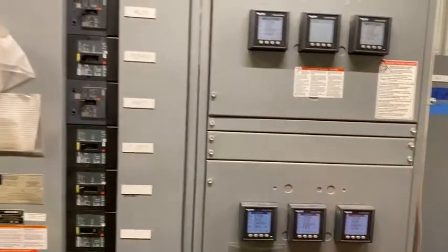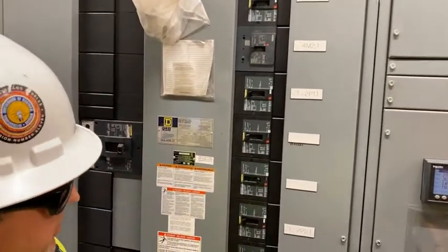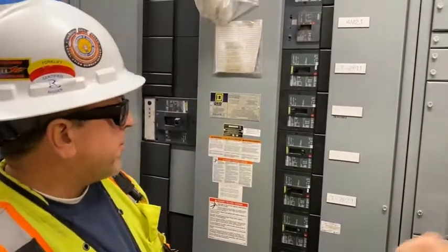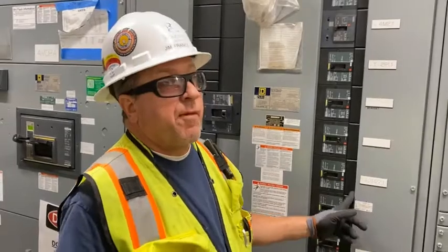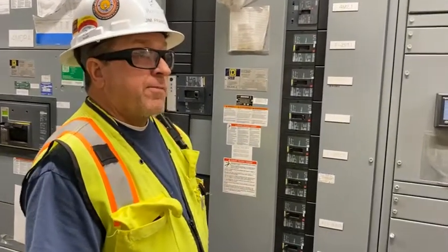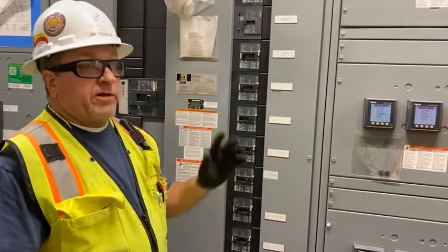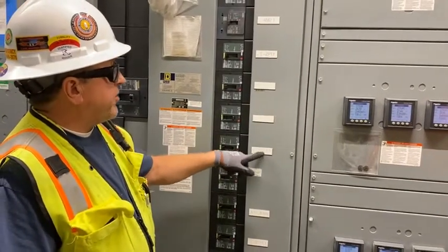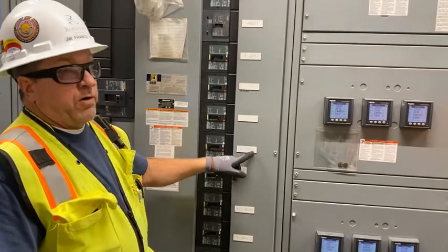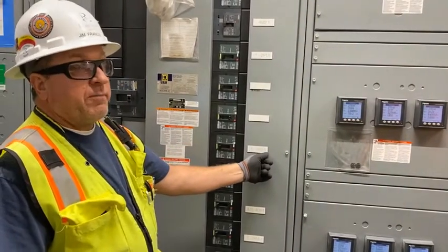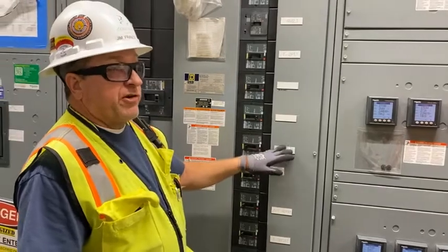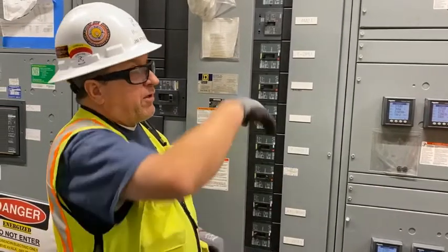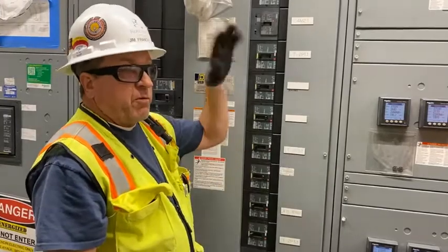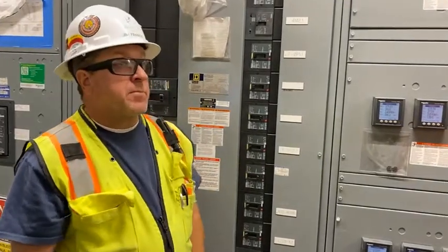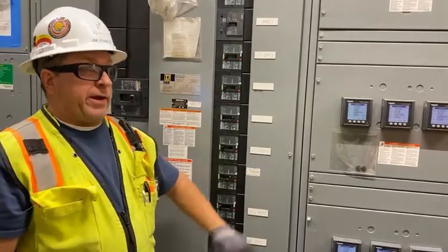So all these here, they're tied to a panel, but like throughout the building too, and electrical rooms and stuff. Well, these are monitoring, for instance, the panels in the rooms, hallways and stuff, up in the electric room. One of these is going to shut one of those down. Yes. If you look at the single line riser diagram, it'll tell you that the transformer for P2.1, that's up on the second floor, goes up at 480, hits a transformer, and then that hits a distribution panel, which will feed the P panels on multiple floors. So if you had to work on one of those panels, you would kill it here, or the main at that panel.